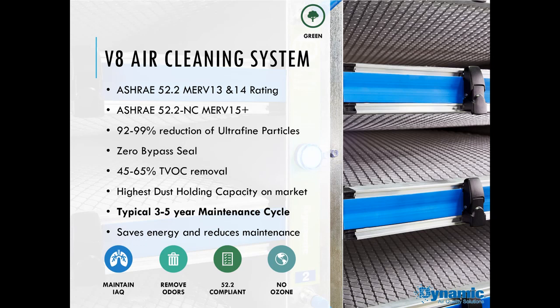Another critical thing is it has a zero bypass seal, meaning that everything goes through the media. That's critical because the HEPA filter standard, for example, is as much about seal as it is about media efficiency. If you've got HEPA filters and you've got a gap this big, you don't have HEPA filters. So seal is important from a performance standpoint. We're also able to take out moderate levels of VOCs, sort of low nuisance levels. We make carbon systems for industrial settings, but typically people don't want those. This has a 10x dust holding capacity versus passive filtration, which typically yields a 3 to 5 year maintenance cycle.